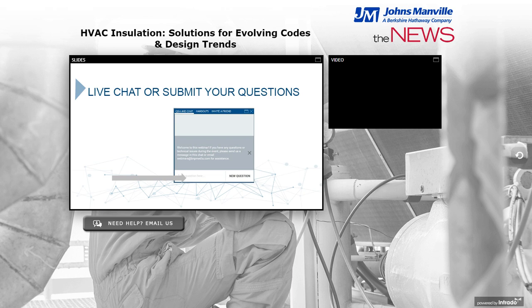I've seen one request so far. I believe it's in the state of Washington, a commercial code requiring any fresh air intake duct running from the louver to the damper—so ducting that goes from outside the building to the inside until that first damper—don't quote me on this, but it's come up recently where they're requiring that duct to match the exterior building envelope thermals. I believe it's R19, and they're asking that duct receive an R19. That's the only one I'm aware of that's been brought up, and I'm still trying to get clarification, but that's the only one I've seen so far.